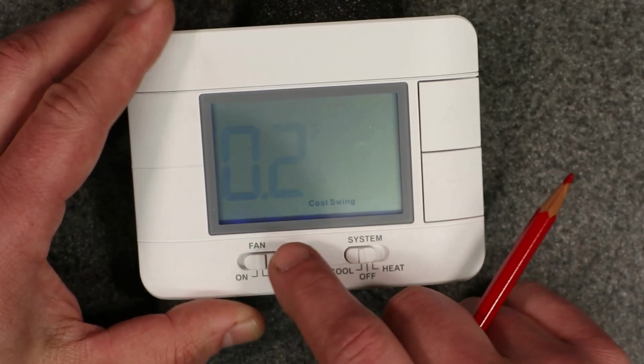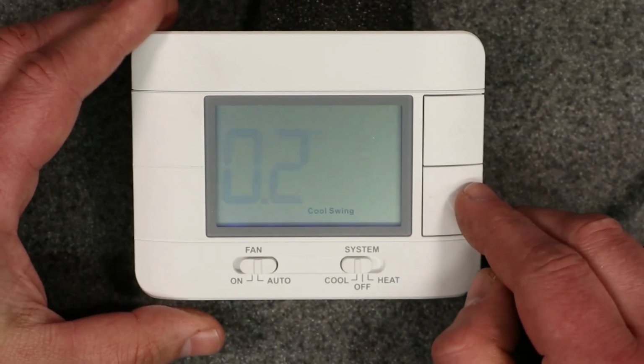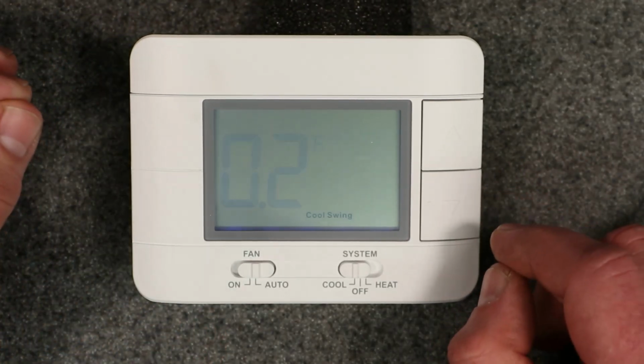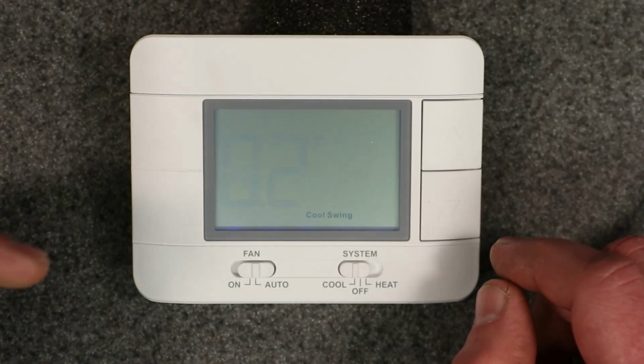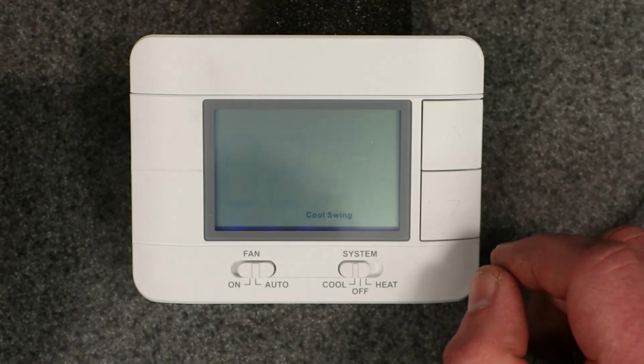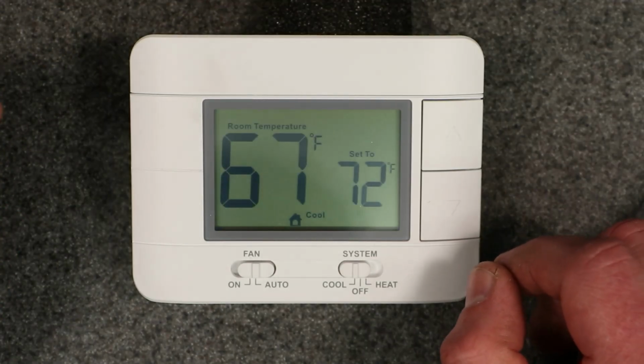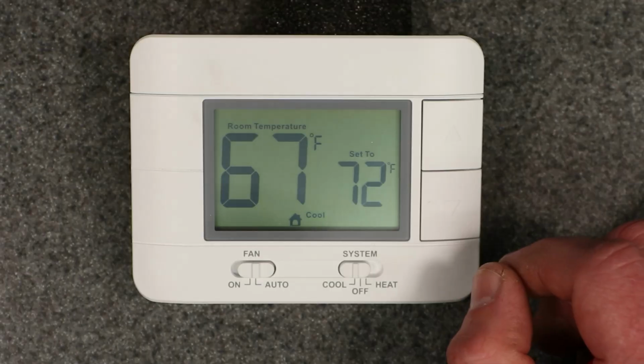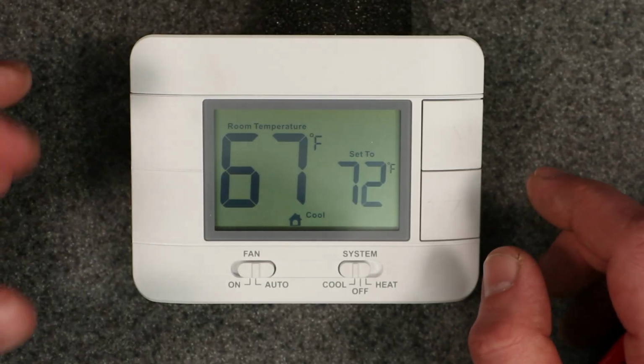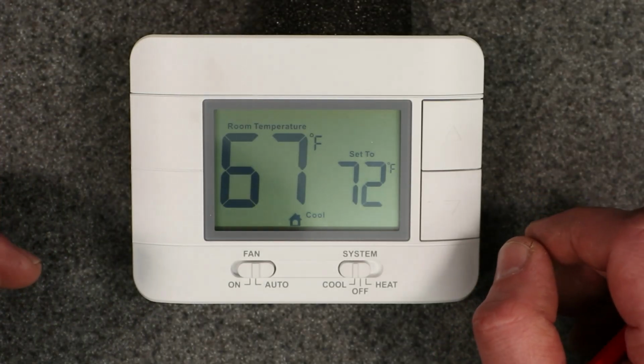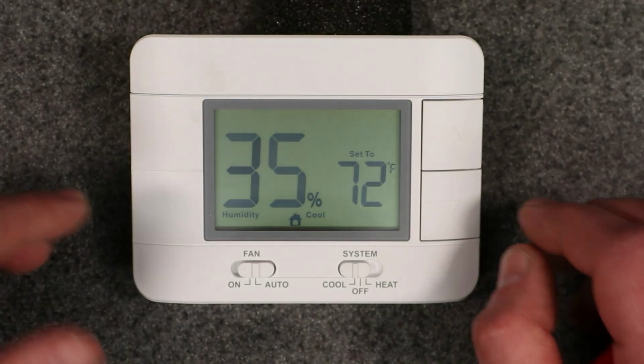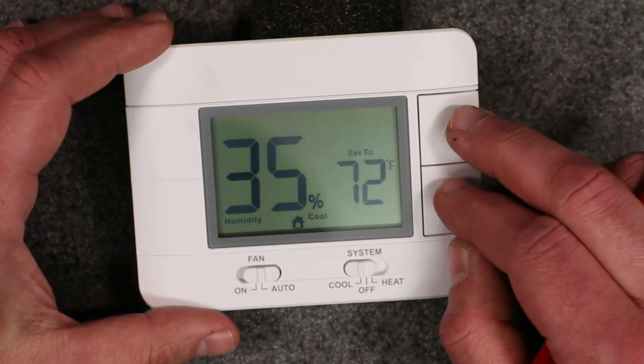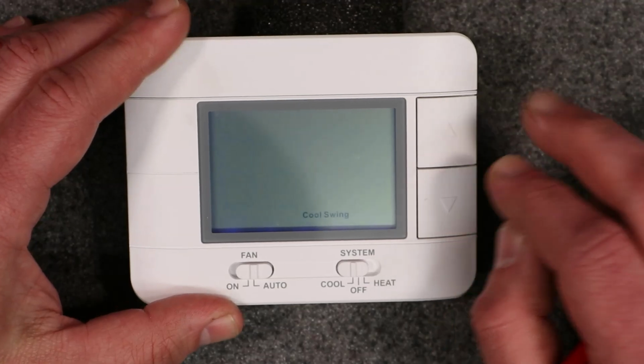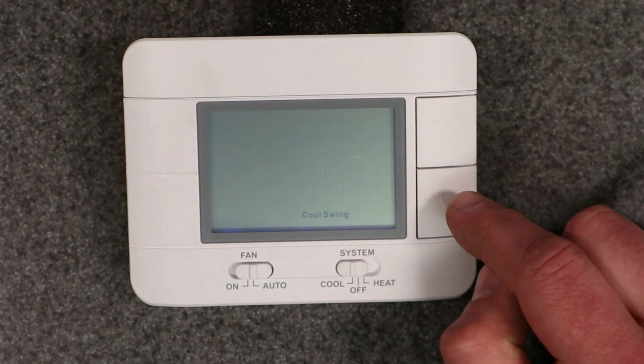You can go all the way down to a really tight 0.2 of a degree for the set point to really switch on immediately when it hits. Say you have it set to 68, and it hits 68, your room heats up and hits 68, it's going to hit 68.2 internally and shut off the heat. Or the inverse if you were cooling. So let's go back into that.